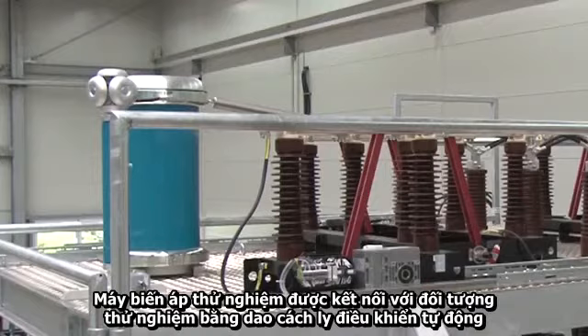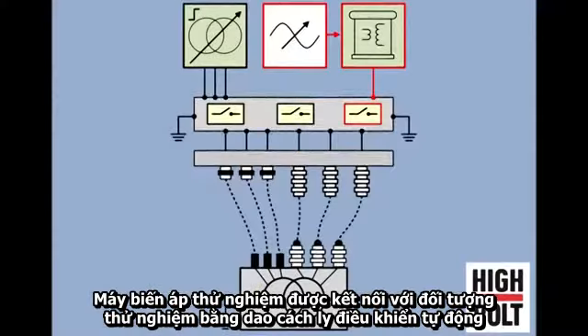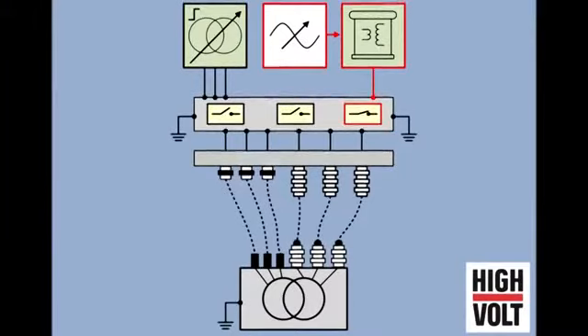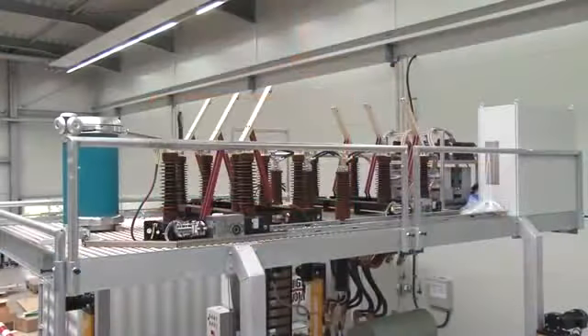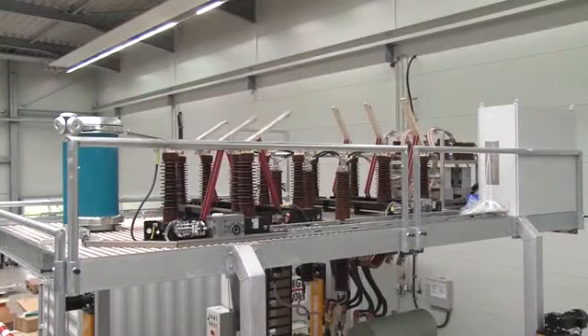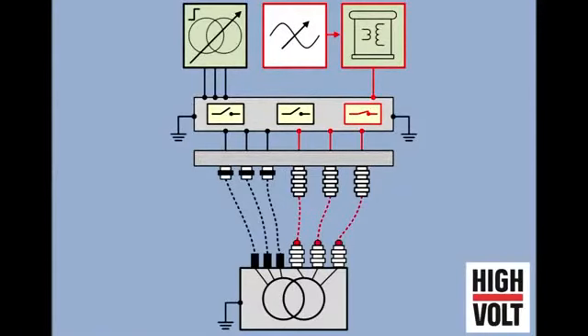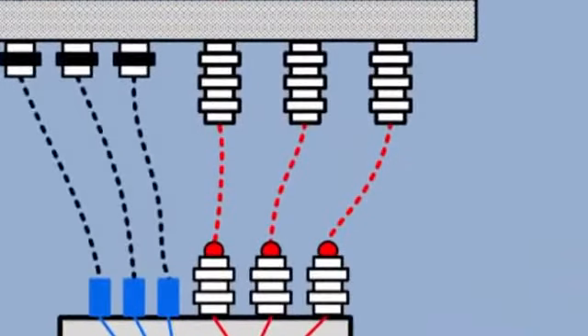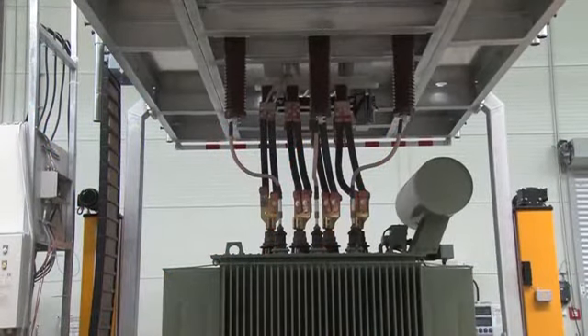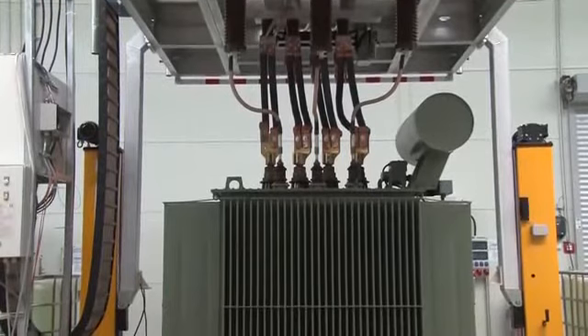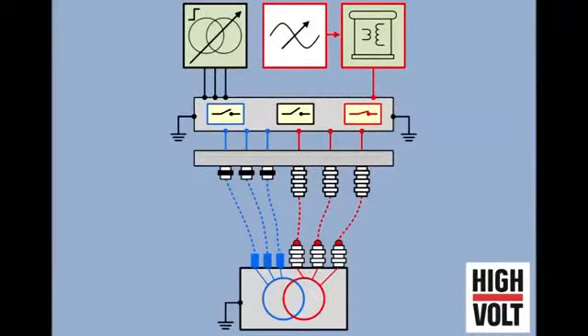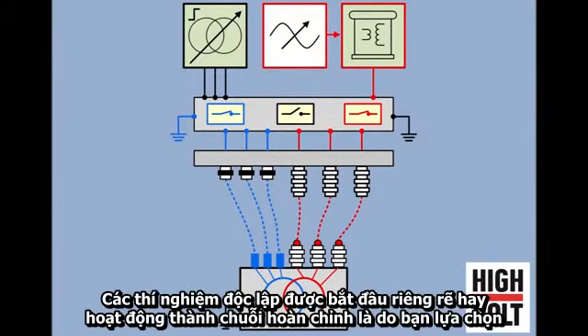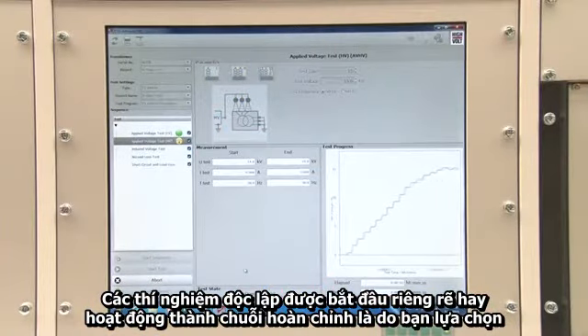The test transformer is connected to the test object by way of automatically controlled disconnectors. The other end of the winding is also earthed automatically. It's your choice whether the individual tests are started separately or run as a complete sequence.